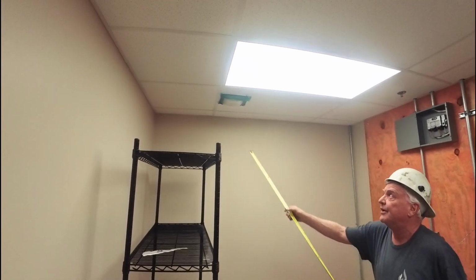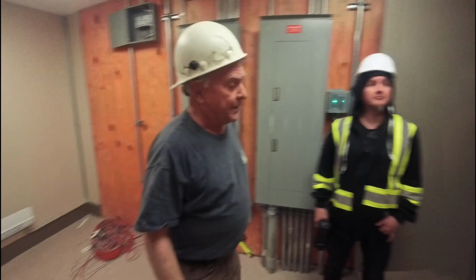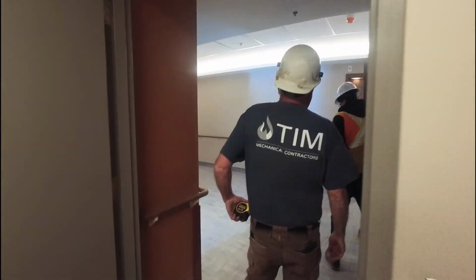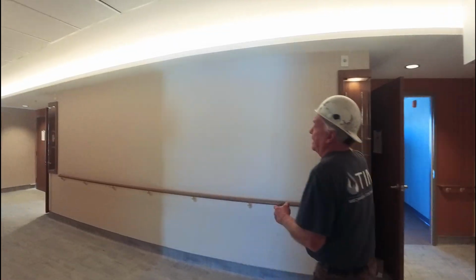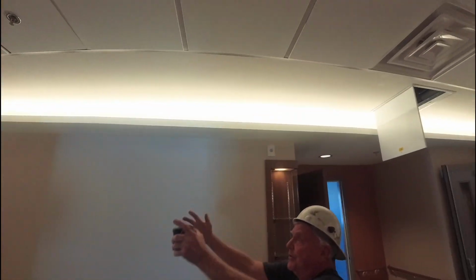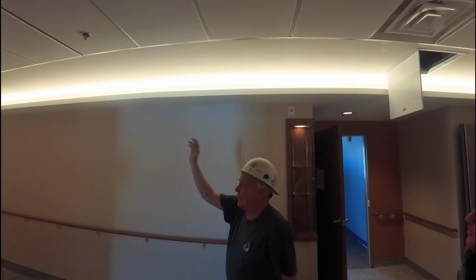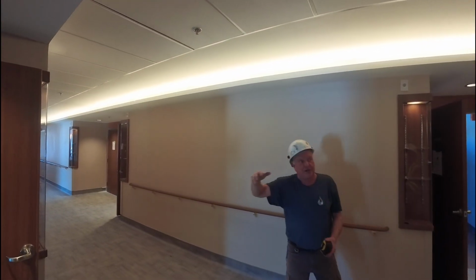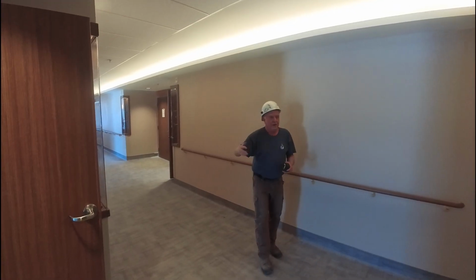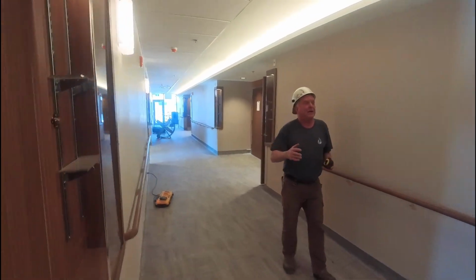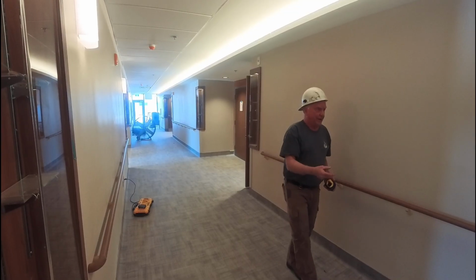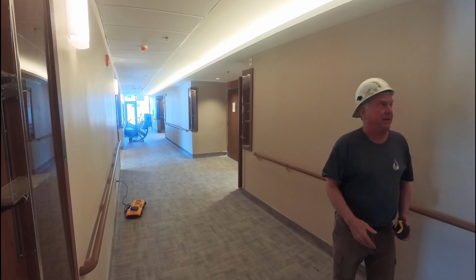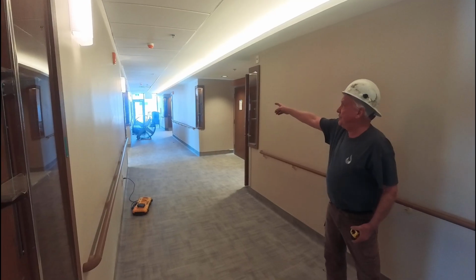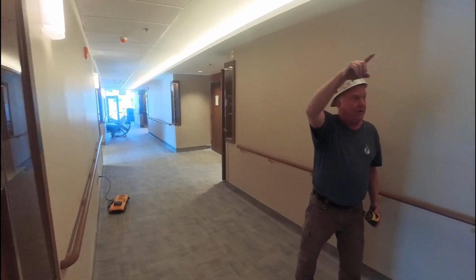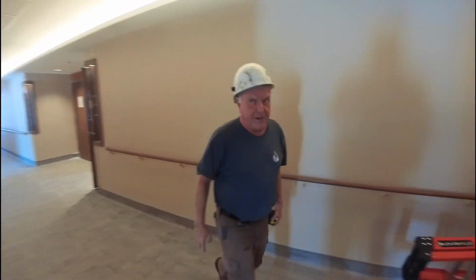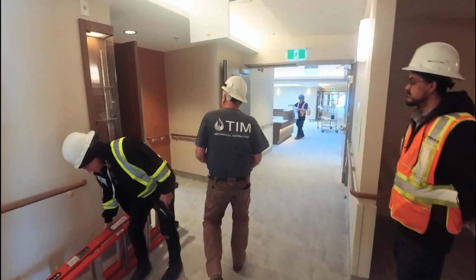Again, another exhaust that's coming from the makeup air. So, a small example is the supply duct and the return duct, or the exhaust duct as we refer to it on the makeup, runs directly down the entire hallway all the way to the end. The duct tapers as it proceeds because you're taking more air off of it, and you need to taper it to maintain the velocity of the air and the speed, like a Venturi effect in a sense, right? We have 2 diffusers in this hallway, which are blowing supply air coming off it.